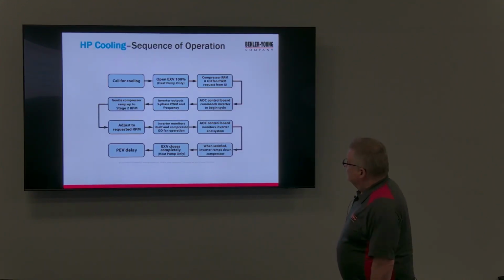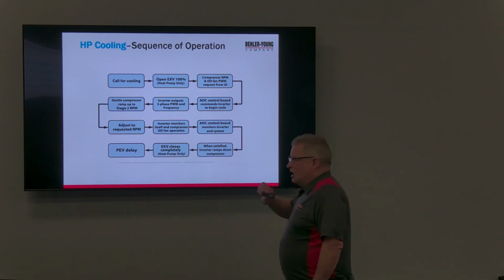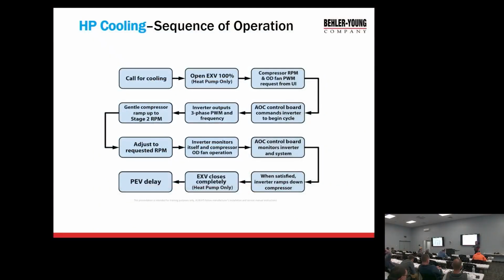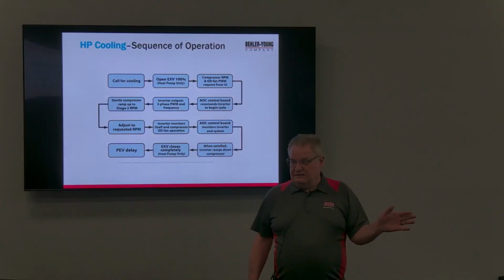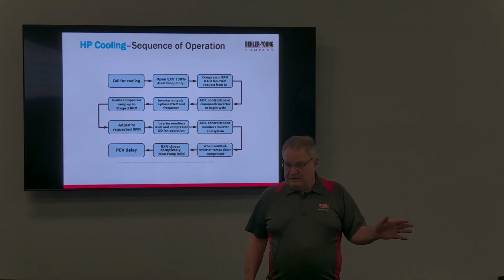Okay. Heat pump sequence of operation. And this is talking about the extremes, the variable speed stuff. Okay, for a call for cooling, the expansion valve on the heat pump is going to run wide open. Well, remember there's two valves, right? One on the outside, one on the inside. So if we're dealing with that electronic expansion valve, that's in the condenser unit. So where Dave showed you that orifice, there's an EXV there instead. So if we're going into cooling, we don't need that valve, right? So it's going to drive the valve wide open.